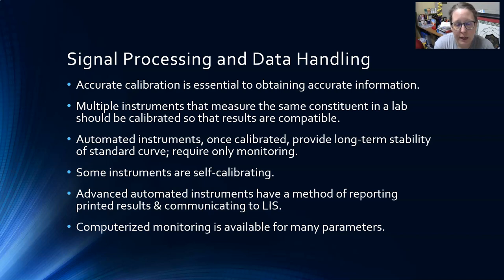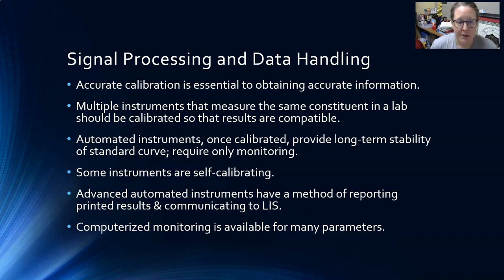Lastly, we have signal processing and data handling. Accurate calibration is essential for accurate testing results. Multiple instruments measuring the same constituent in the lab should be calibrated so results are comparable — for example, running glucose or creatinine on machine A or machine B should give the same results. Automated instruments, once calibrated, provide long-term stability of the standard curve and require only monitoring. Some instruments are self-calibrating.